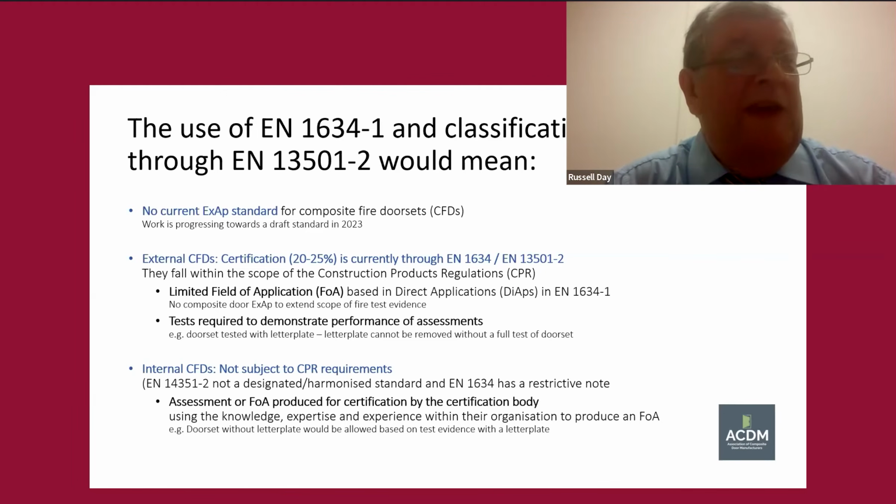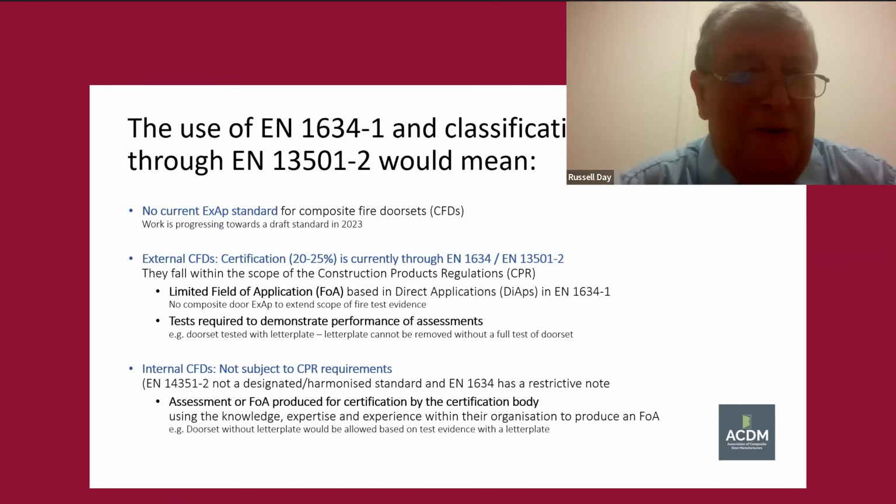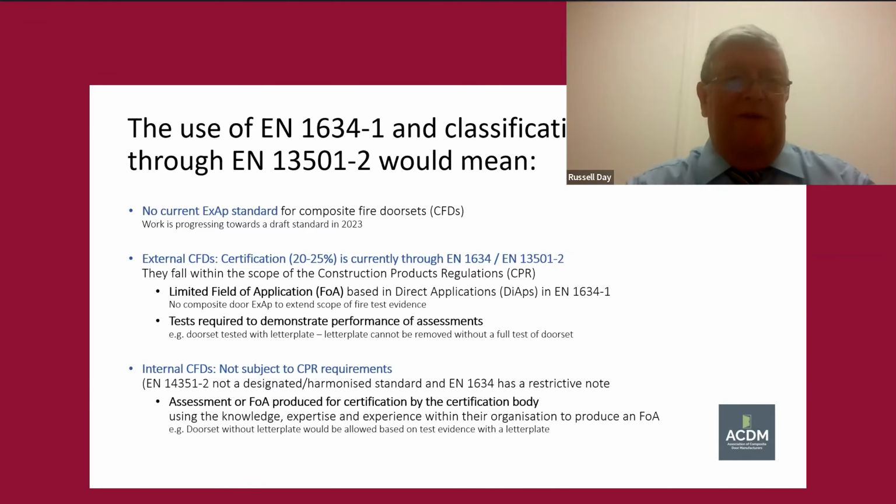They had a request for the door letter plate to be removed, in other words, not cutting a hole in the door. And they couldn't do that without another full test, because the DIAPs within 1634 Part 1 do not allow that to happen. Whereas within an extended application, which we're in the process of writing at the moment, that would be allowed, because you're actually making the door less vulnerable by not cutting a hole in it. But that's a typical example.